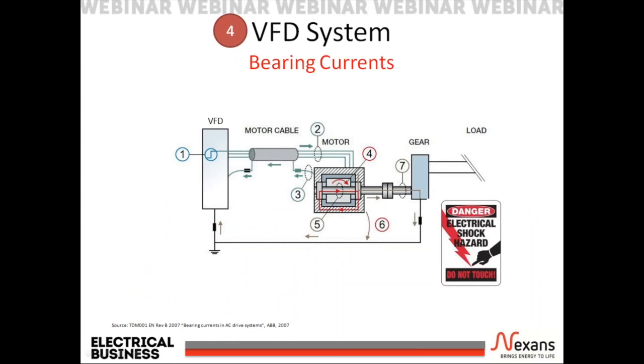The motor will move the rotor shaft based on the fundamental waveform, or the low frequency component, and reject all the other frequencies, effectively acting as a filter. The currents range from a few hertz all the way up to the 100 megahertz range. These low and high frequency currents will look for the lowest impedance back to the VFD. If you're using the wrong cable for your system, then these currents may return to the VFD by another means, resulting in motor frame electrical shock hazard, ignition source for hazardous locations, motor and driven machinery bearing currents, and electrical interference with external wired or wireless systems.